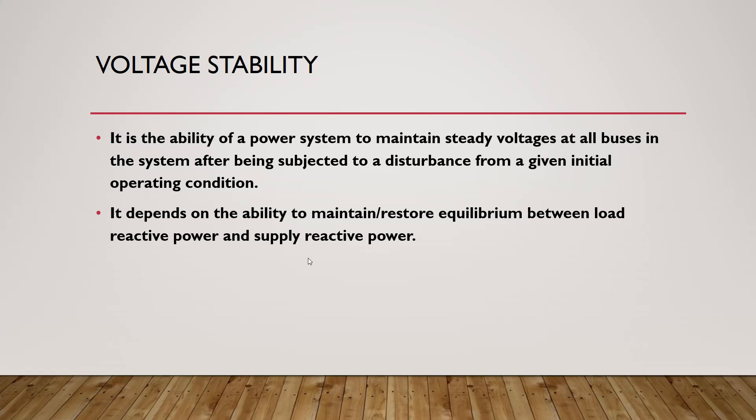Remember that reactive power is highly related to voltage. The reactive power of our load Q equals the voltage squared divided by the load reactance X: Q = V²/X. So Q of our load depends on our voltage. If our supply is able to satisfy the reactive power required by the load — giving it enough Q — then we can have a steady-state voltage.